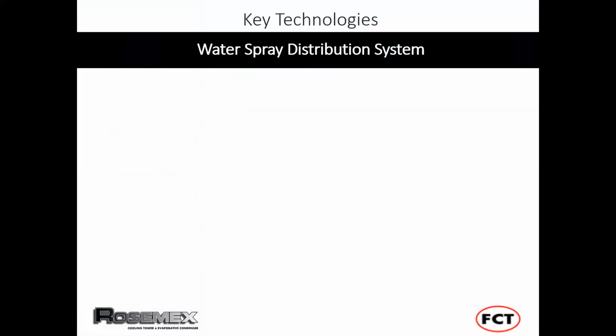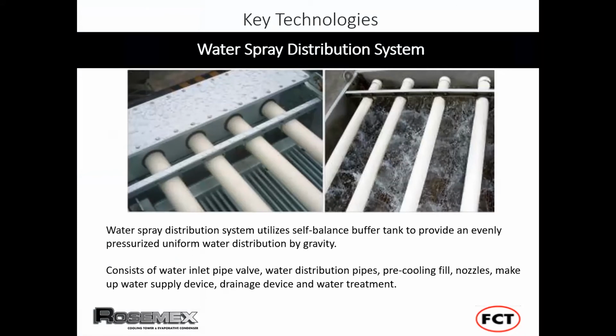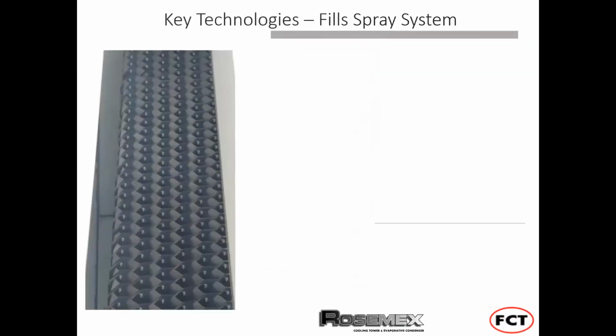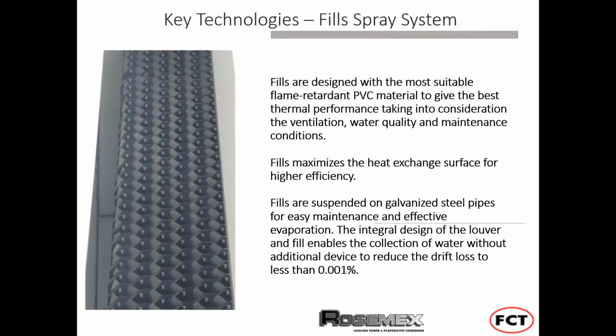Some of the key technologies that we use are the water spray distribution system, which utilizes a self-balanced buffer tank to provide evenly pressurized uniform water distribution by gravity. It consists of water inlet valve, water distribution pipes, pre-cooling fill, and nozzles, which all make up the water spray distribution system. The other one is the fill system, designed with flame retardant PVC material to give the best thermal performance, taking into consideration ventilation, water quality, and maintenance. Fills maximize the heat exchange surface for high efficiency. Fills are suspended on galvanized steel pipes for easy maintenance and effective evaporation.